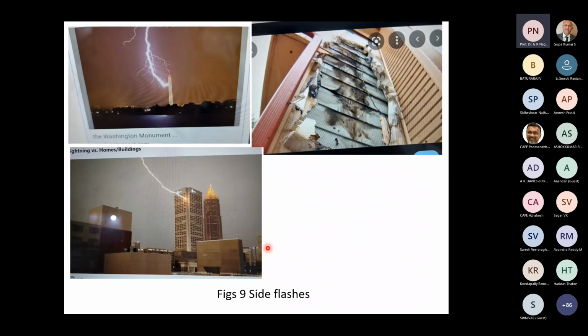So this is the principle of the rolling sphere technique. Now, I have given here 3 photographs in which side flashes occurred. You find that this is the Washington Monument, where one of the leaders has branched and hit the top of the monument, but the main stroke has occurred on the side here. And this again, you will see that on this very tall building, the stroke has come and hit the side surface of the building, that too at a corner. Obviously, corners and edges are very sharp. Therefore, streamers develop very quickly, much earlier there than in all other regions. Therefore, they need the most important consideration in designing lightning protection. See, it is the corner here. You see here the damage caused by a side flash, extensive damage caused by a side flash. If lightning protection is not provided, we must be prepared to face such extensive damage.